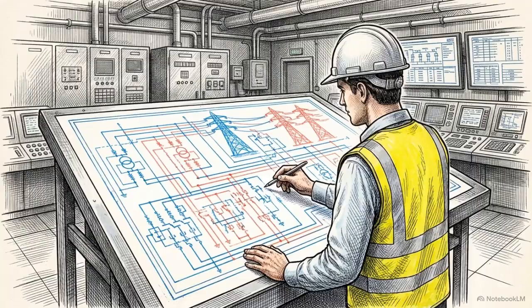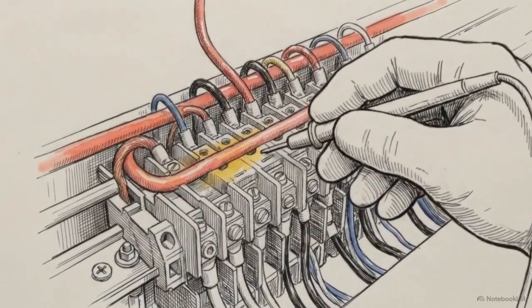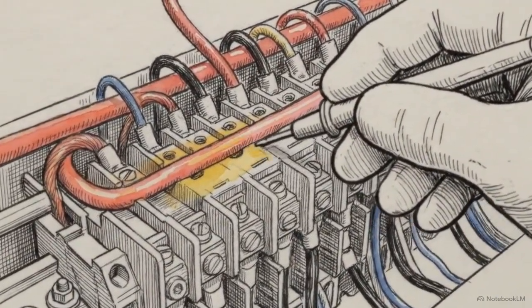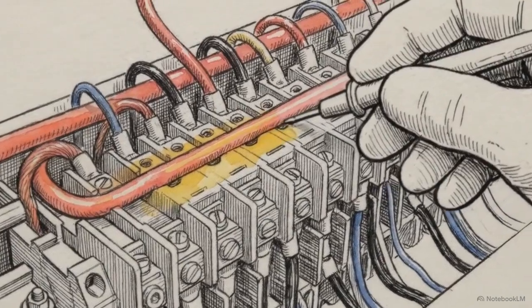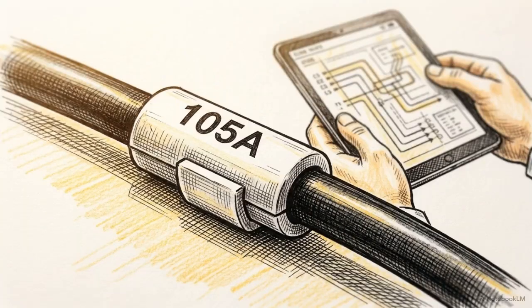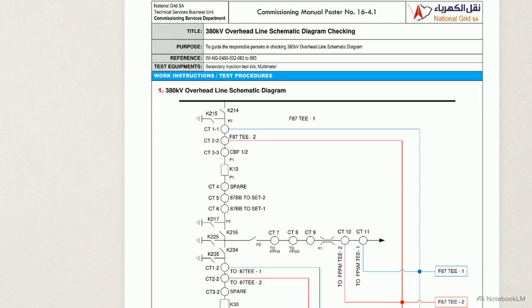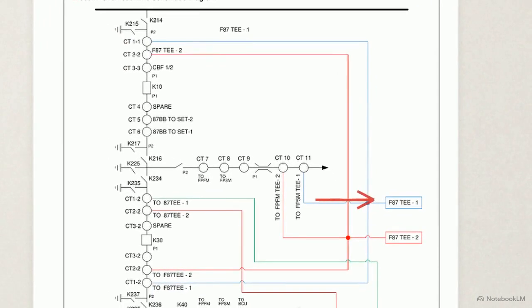We now transition to the passive protection domain. For high-voltage 380 kV infrastructure, the engineering design requires strict point-to-point drawing validation. The tracing principle is absolute. We follow every physical wire from its source terminals directly into the primary protection relays. The physical reality must perfectly match the approved schematics. This 380 kV overhead line schematic maps the paths we trace from the current transformers on the left to the primary protection relays on the right. We verify line differential, distance, and breaker failure paths.